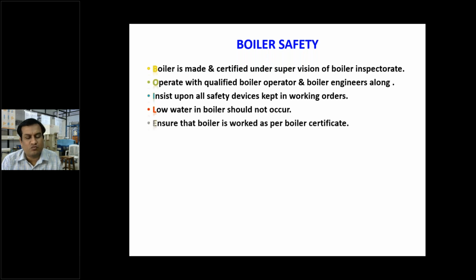Ensure that the boiler is working as per the boiler certificate. So whatever the points mentioned under these certificates, mainly I have discussed that the working pressure or the design pressure, then the maximum temperatures, the fuel for that boiler, the thickness and material of construction of all these boiler mountings and accessories. So you have to ensure that the boiler works as per the boiler certificate.